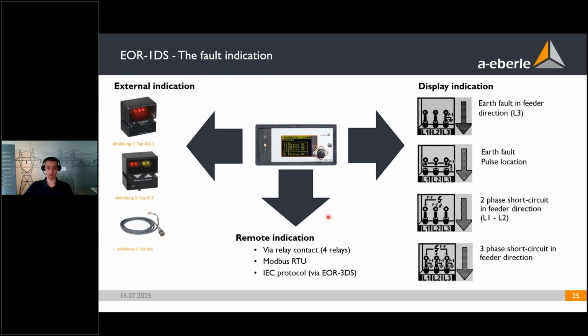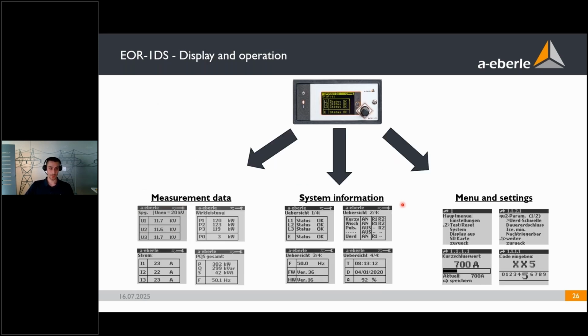Or you could also use a EOR-3DS for this. And this device would also be able to convert from Modbus RTU to an IEC protocol. The display also offers a few other views. One would be measurement data, as you see here, voltage, current for each of the phases. Also reactive power or your total powers. So here's active power, sorry, or your total powers. So active, reactive, and apparent power. Also your frequency measurement. So all your measurement data.